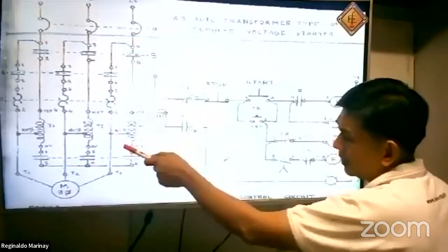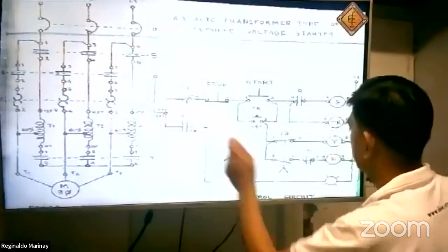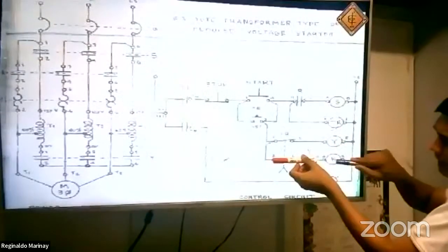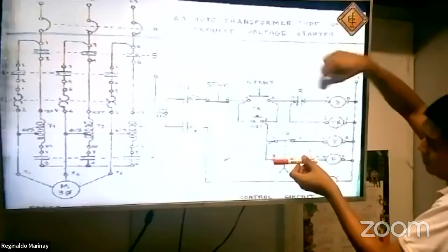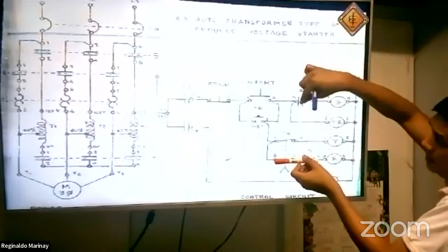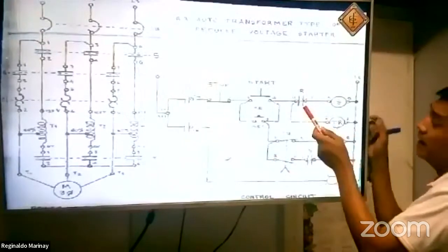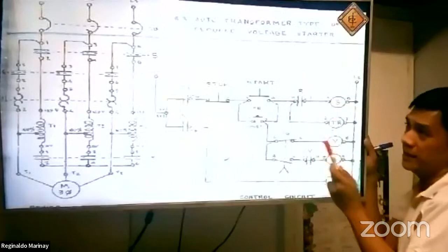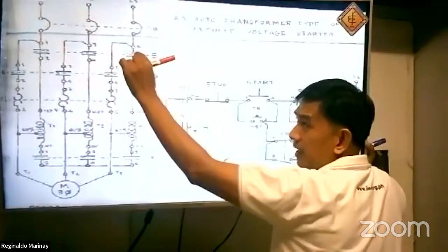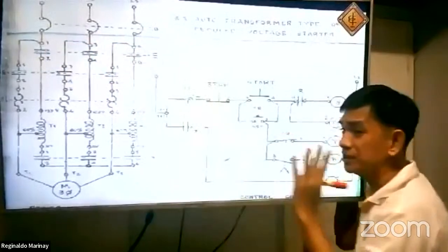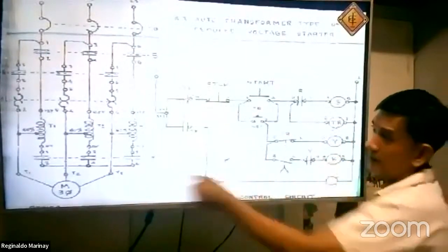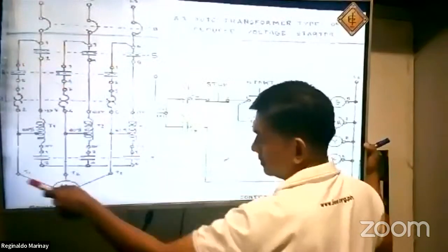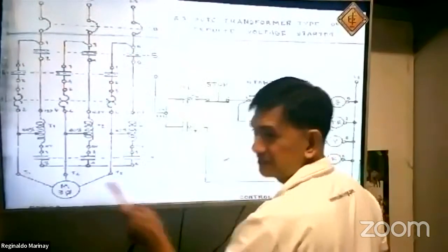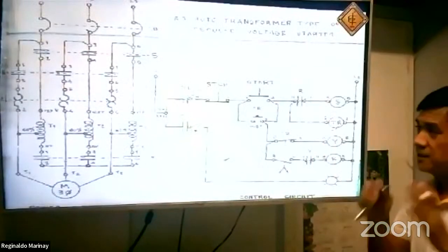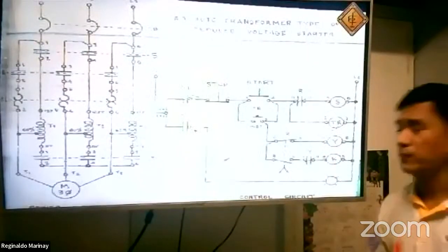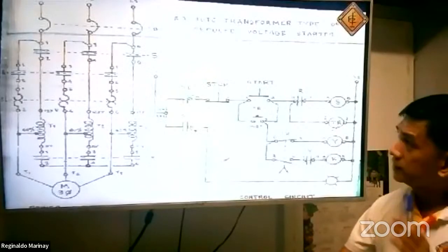Why will it not flow to your transformer? Because the R here becomes energized, and the 11 and 12 of R will become open. That simply means you de-energize the S. If you de-energize the S, 1, 2, 3, 4, 5, 6 will become open, going back to its original position. You energize the R, this will become closed, the current will flow here. I hope you are getting me. So that is the basic idea of the autotransformer motor control or reduced voltage starter.